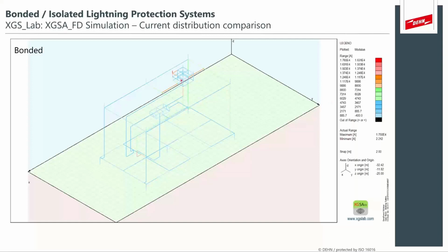Now, look at the grounding bond, the indirect grounding, or the metal bodies' grounding bond that goes into the structure. You've got all these metal ducts, like I showed in the previous picture, and it all goes down to this main earth bus bar. Now see the amount of current. You can even see the color, orange, there's some green, and they all diverge and come back to this main earth bus bar where it gets red again.